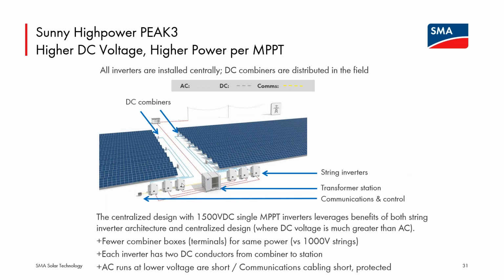The general layout we would expect for the PEAK3: while it is possible, for a very large PV array field, to have the inverters spread throughout the array field, we almost always recommend to customers that you adopt a centralized plant design. That is, while you have smaller power conversion units, you still lay them out as you would a central inverter, with very few spots throughout the array field where you're consolidating the inverters.